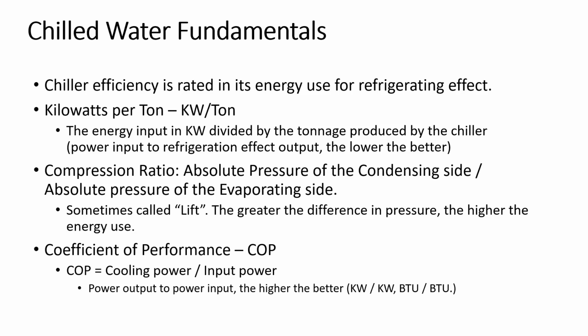Then we get the coefficient of performance. We talked about that in the absorption side. We can do this comparison, but you have to convert power to power. So it's not a comparison of BTUs to power, or power to BTUs, like in kW per ton. Instead, you got to compare BTUs to BTUs, input to output.